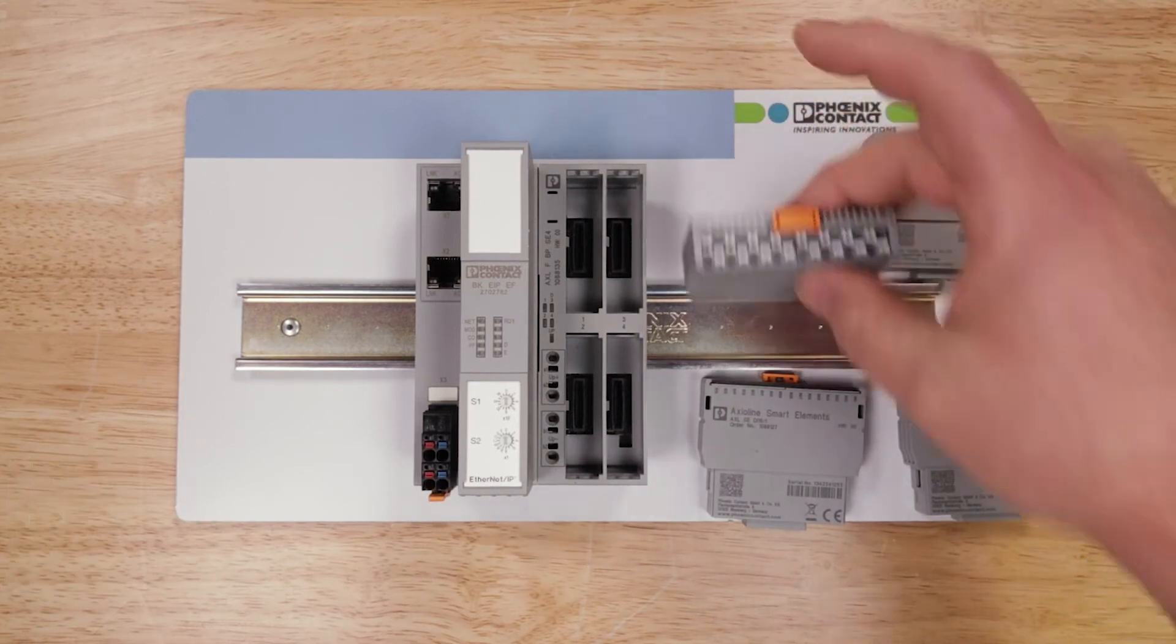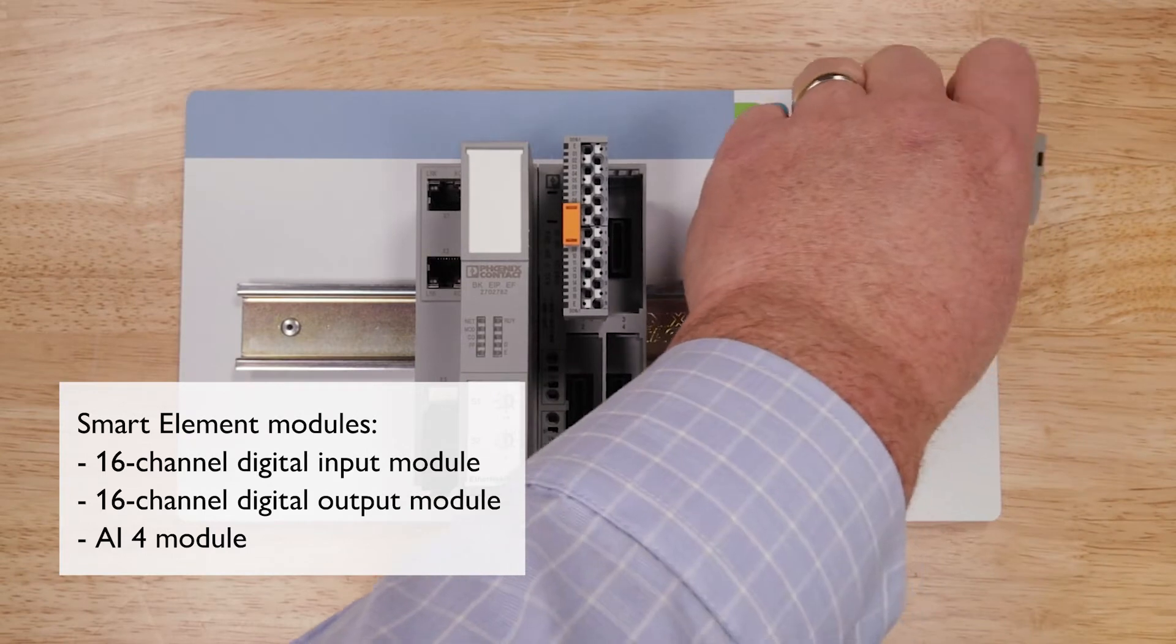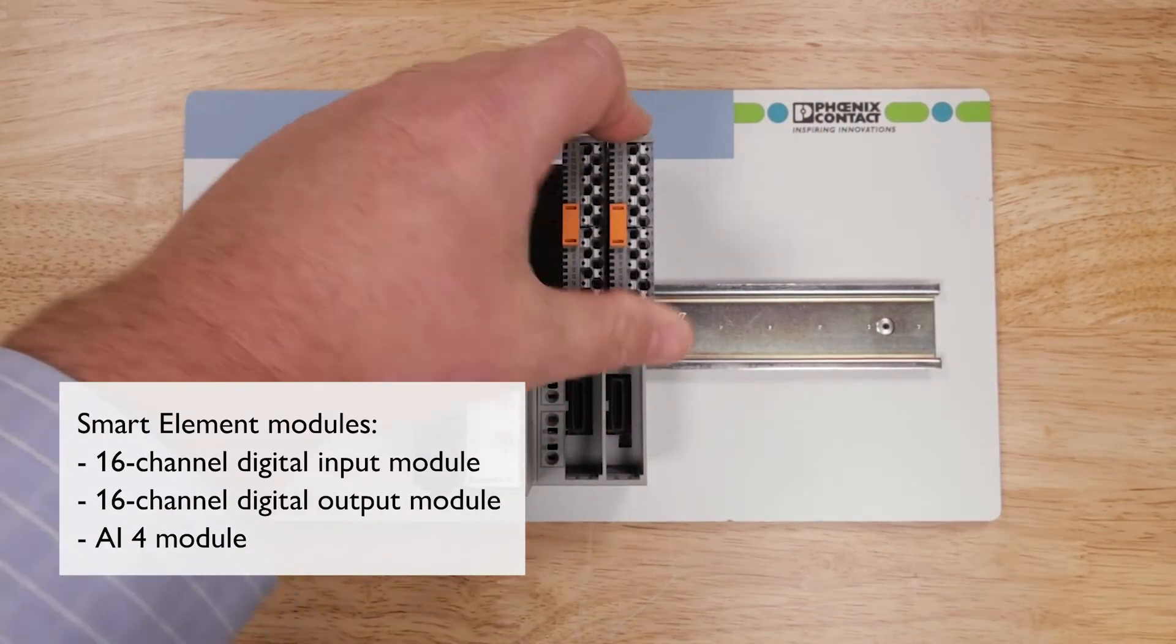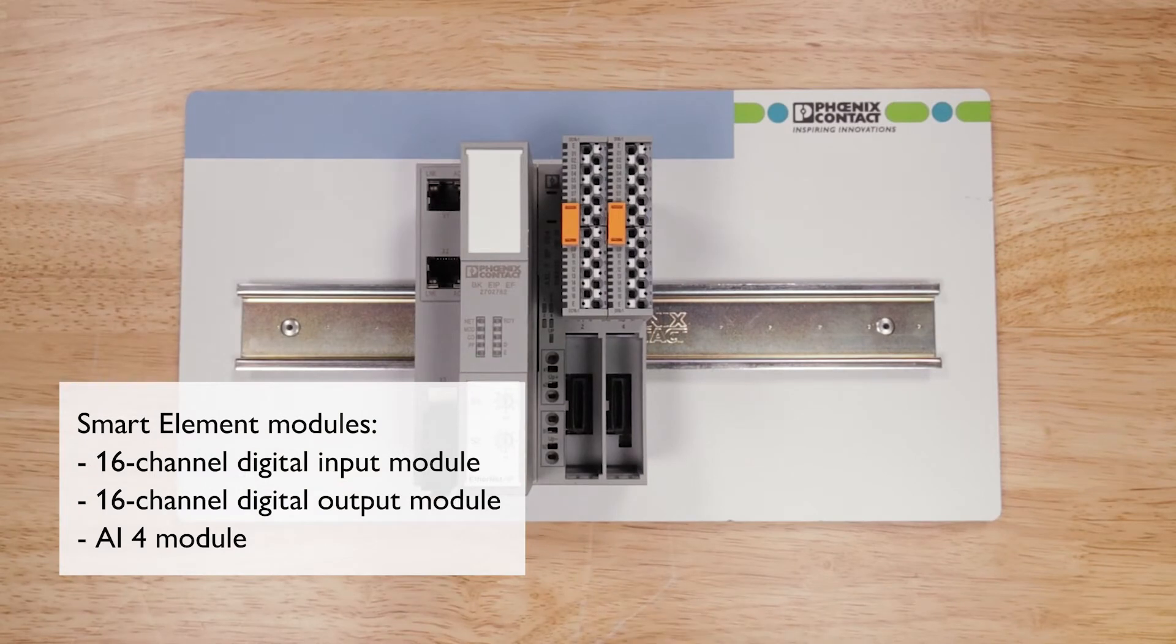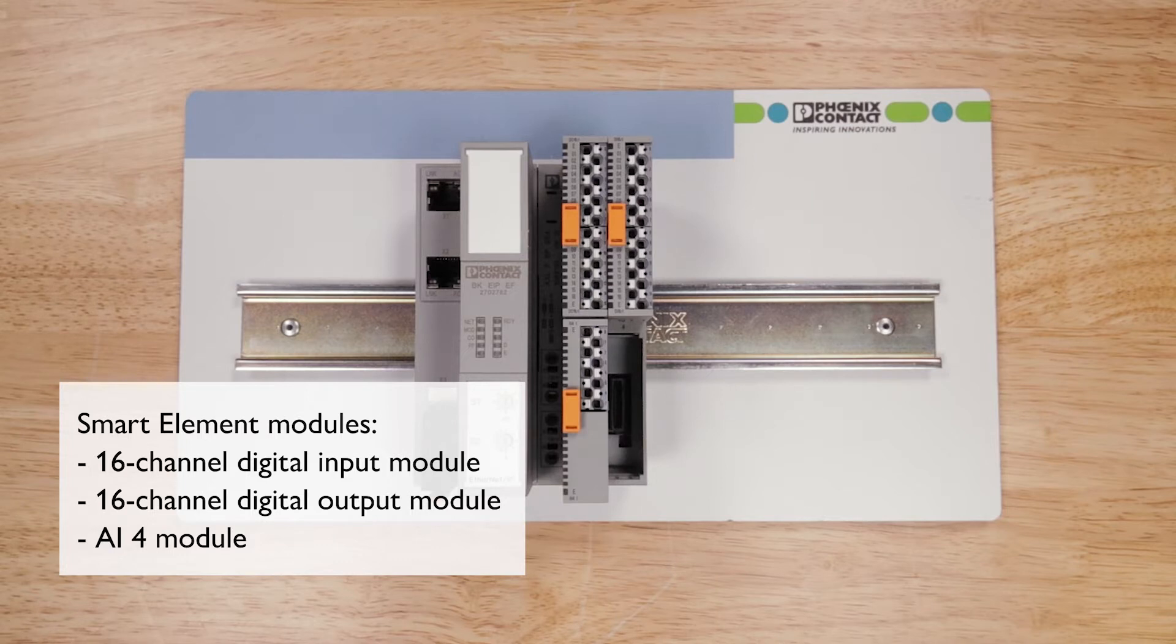For the Smart Elements, I have two digital modules, a 16-channel digital input module and a 16-channel digital output module. You can see I simply snap them onto the rail. And I have an AI4 module, so I have 16 digital inputs, 16 digital outputs, and 4 analog inputs.